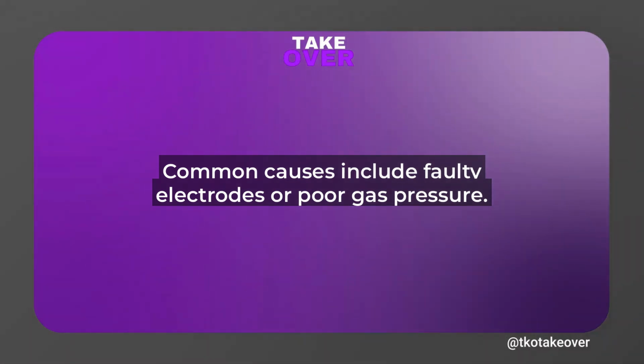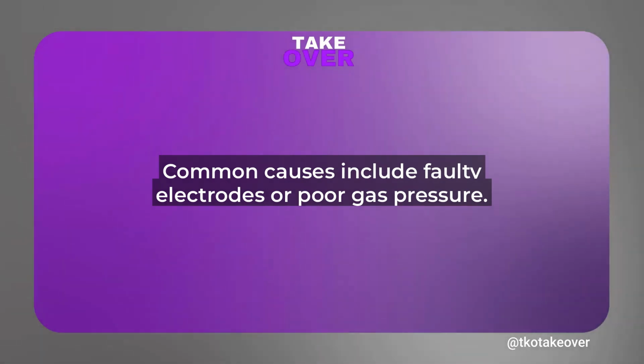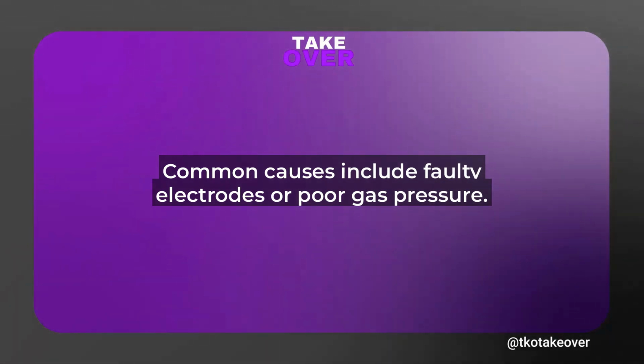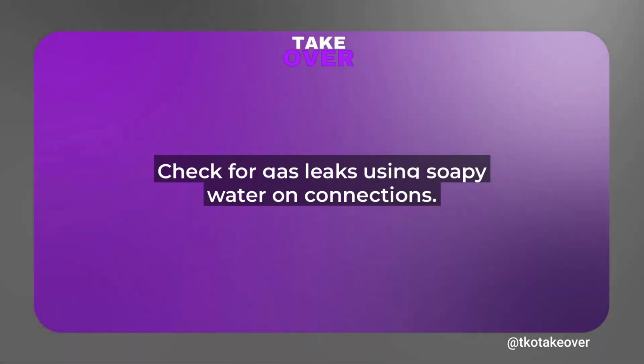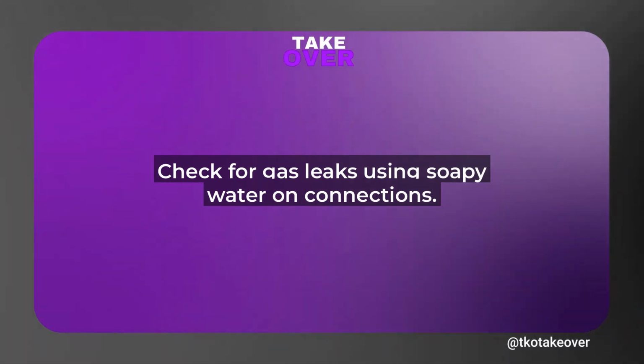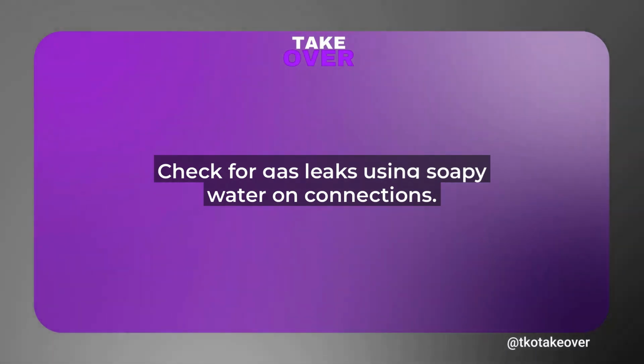Error code A05 often occurs due to issues like a faulty ignition electrode, poor gas pressure, or even a blocked flue. It might show up as a flashing light or an error message on your boiler's display.